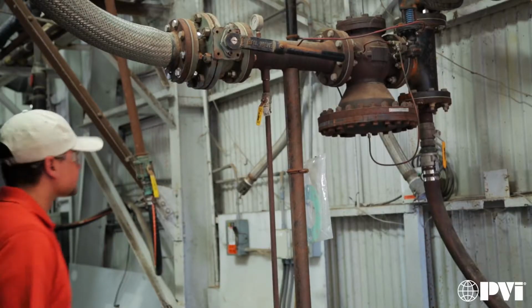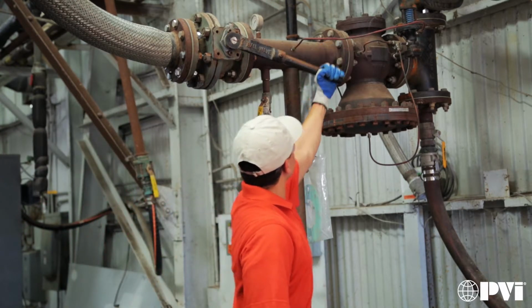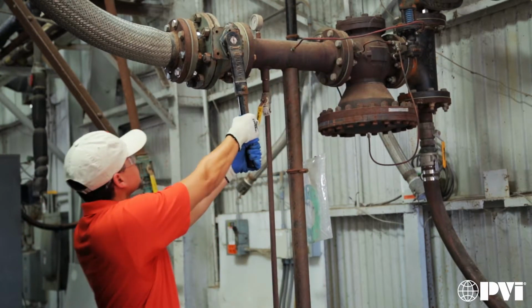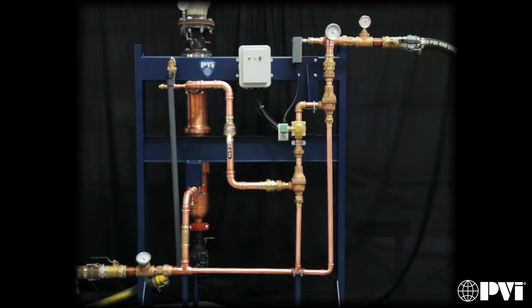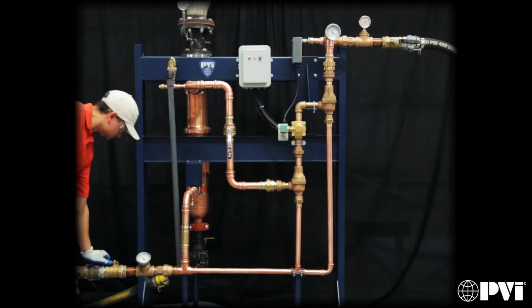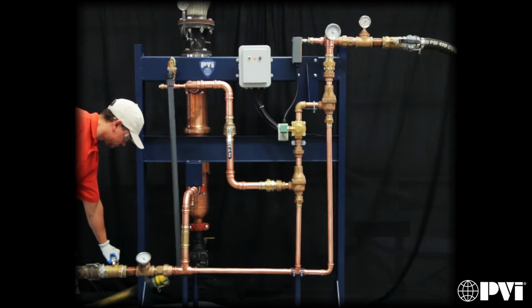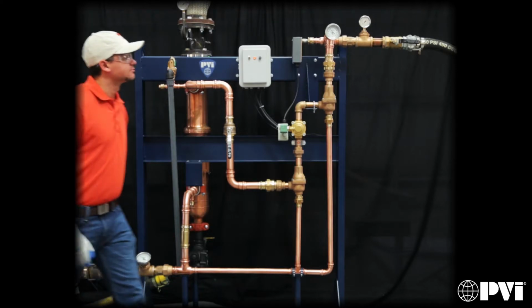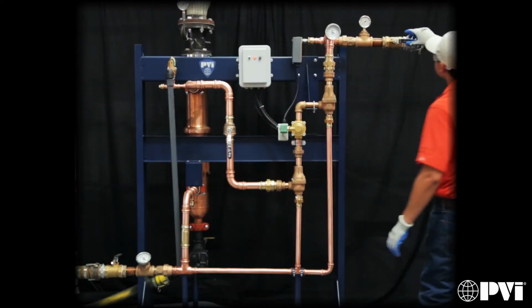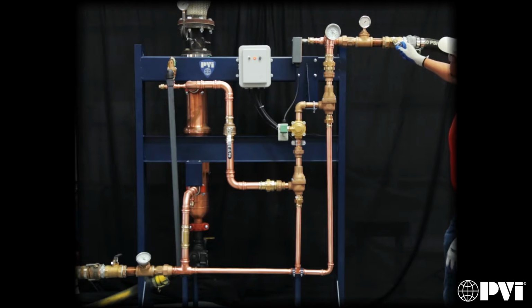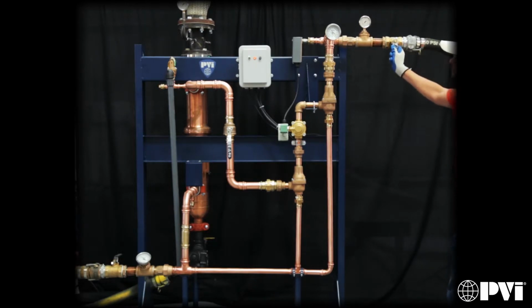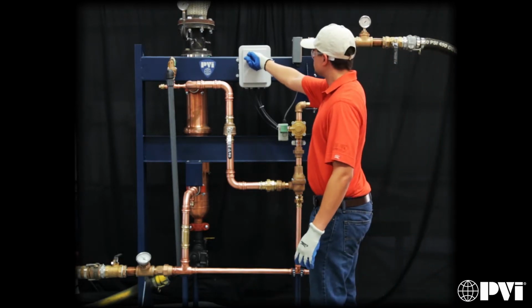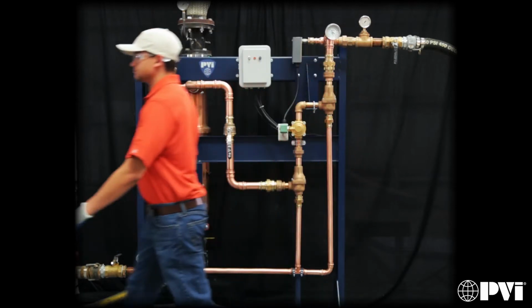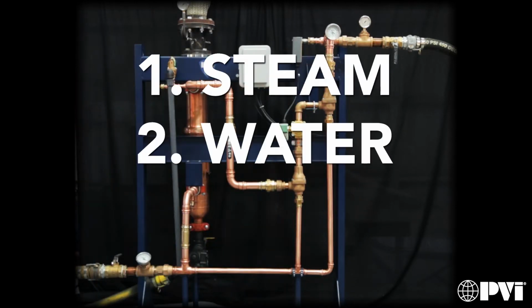To shut down the unit for maintenance. In order, valve off the supply of steam to the heater first. Allow water to flow until heat exchanger runs cold. Then close the water inlet valve, then the outlet. Disconnect electrical power. Remember the shutoff sequence: steam, then water, then electricity.